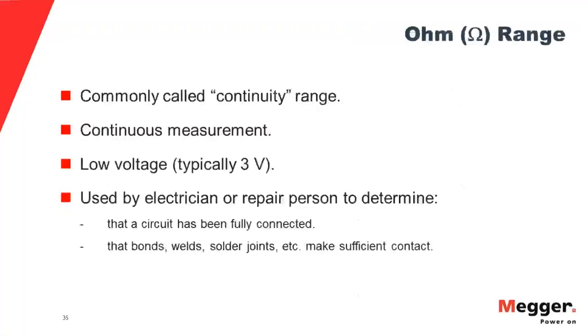And we'll look at a couple more of the functions. Your continuity range. Most of your medium voltage testers don't really need that and don't have that in there, but your 1 kV testers virtually all have a continuity range in there. This is low voltage, low resistance. It's for the opposite side of insulation, which is circuitry. It's a means of telling you that your circuit has been properly connected, there were no wrong connections made at a junction box, and that all your bonds are good. So on a continuity test, you test your circuit, and you want to see an ohm or something like that. And if there's a problem anywhere on the circuit, you get a higher number, and you know that there's an issue that has to be corrected.